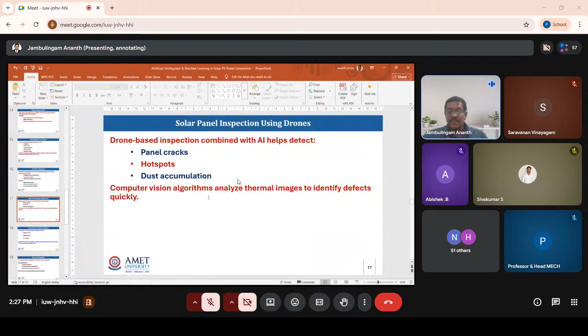By using thermal imaging technique, you can locate hot spots in the panel, and determine the amount of dust accumulation on the surface of the solar panel. Dust accumulation is a major problem when wind speed is higher—the amount of dust accumulated increases, which reduces the radiation reaching the panel surface and leads to a drop in efficiency of the entire system. So drone-based inspection utilizes computer vision algorithms to analyze thermal images and identify defects very quickly.